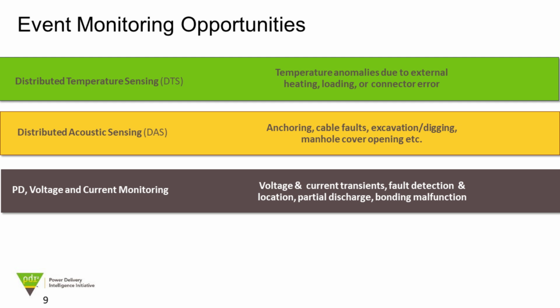And then there is partial discharge monitoring as well as other, let's say, key parameters that can be monitored. I cannot comment on the examples that the audience shared, whether online PD worked or didn't work, but I think that, again, if there's been a near or power frequency test performed during commissioning, followed up by a PD, let's say a permanent monitoring solution, the likelihood of finding issues coming up during the life of the asset is quite high in my opinion.